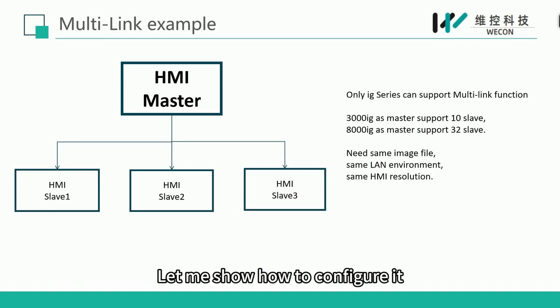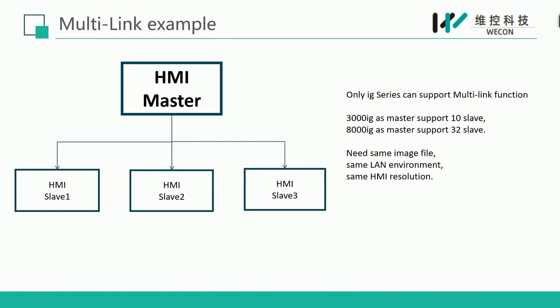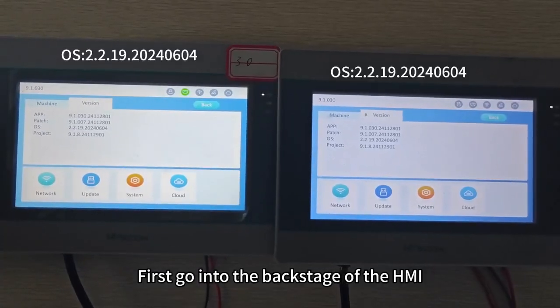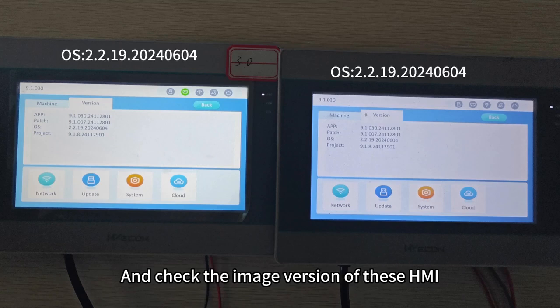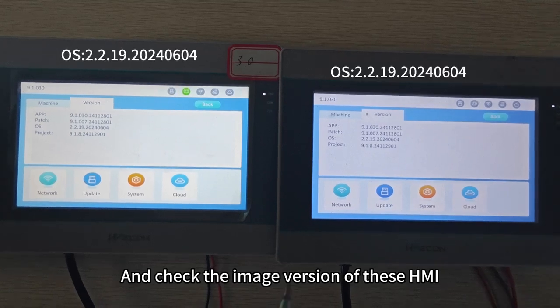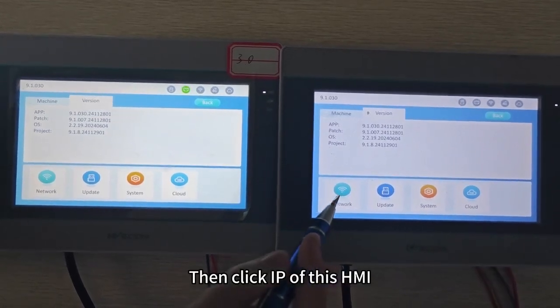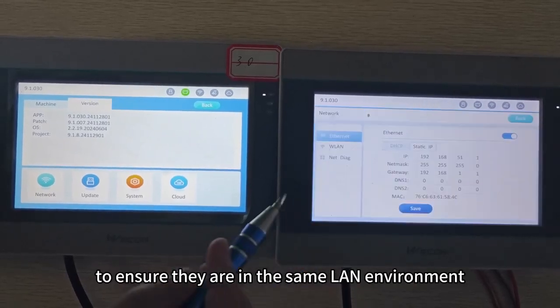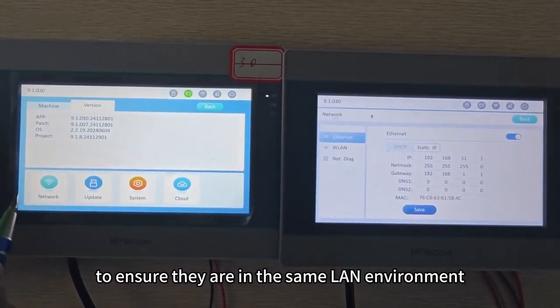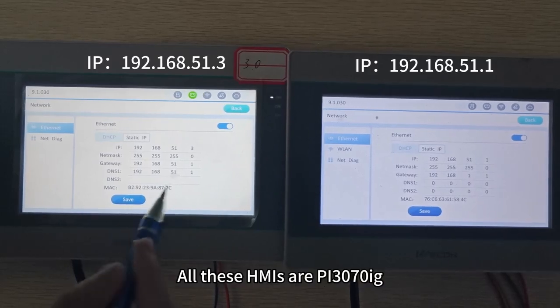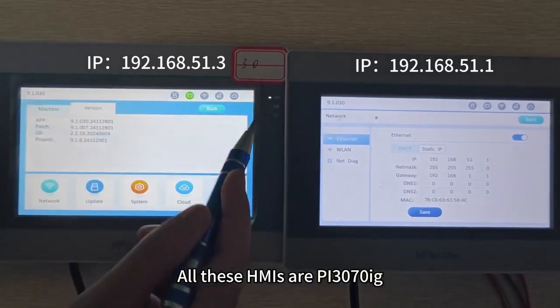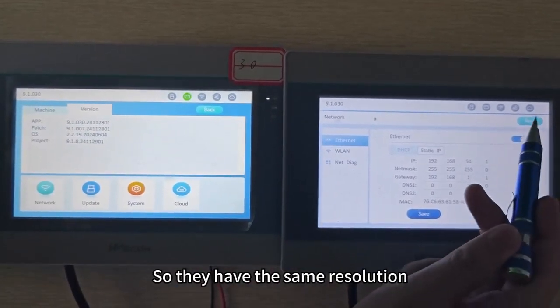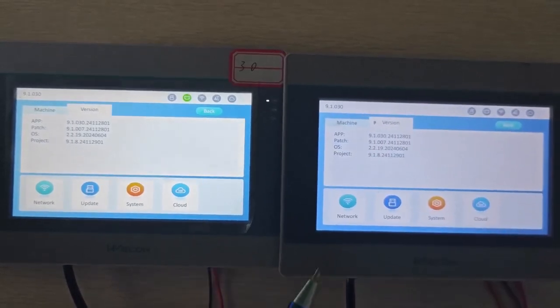Now, let me show you how to configure it. First, go into the backstage of the HMI and check the image version of these HMIs. Then, click the IP of these HMIs to ensure they are in the same LAN environment. All these HMIs are PI3070 IG, so they have the same resolution.